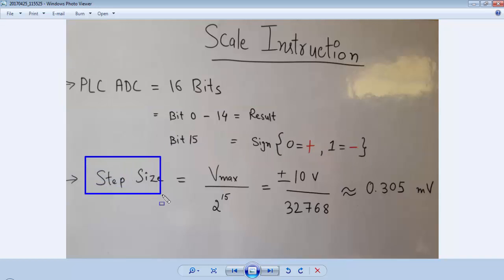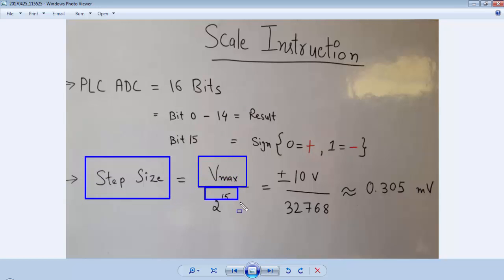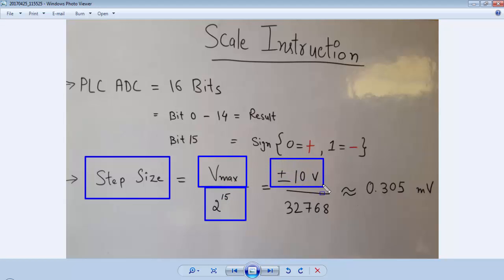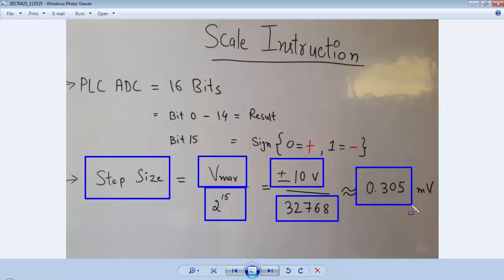The next term related to the PLC ADC is step size. Step size is equal to V_MAX divided by 2 raised to power 15. Since the voltage input card range is ±10V and 2 raised to power 15 is 32768, after division the approximate step size value is 0.305 millivolts.